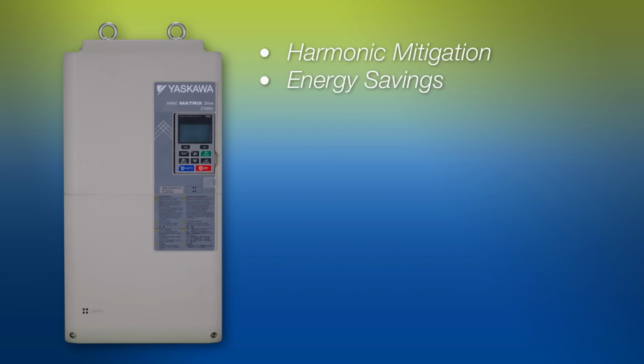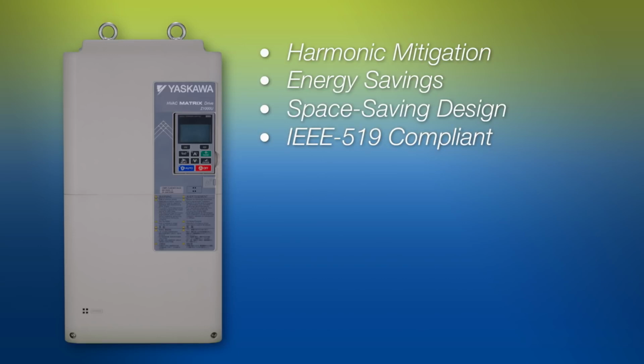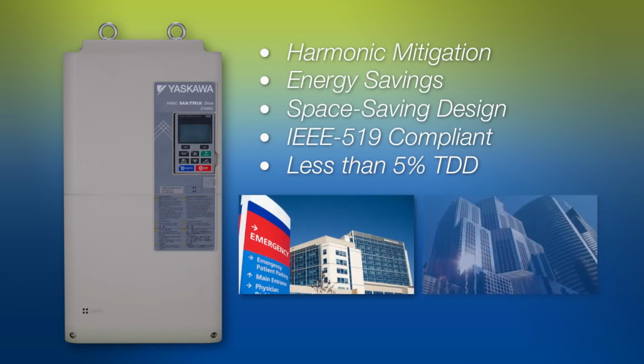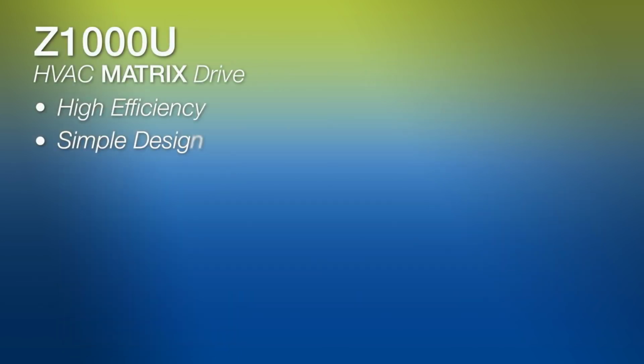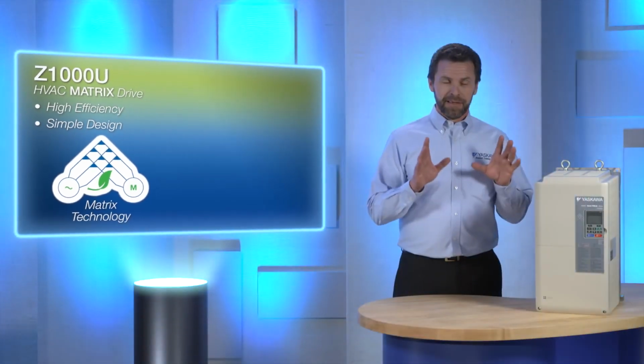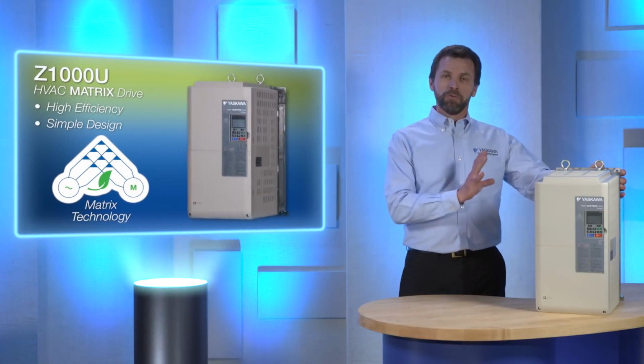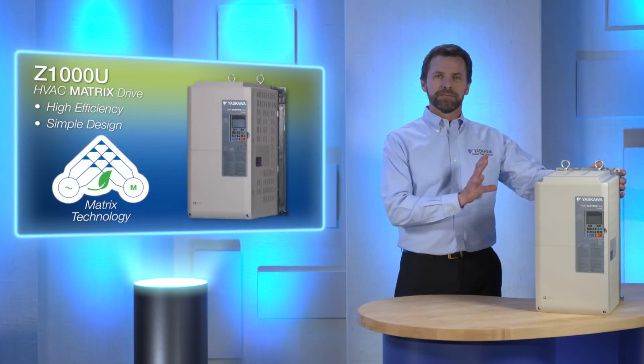It is ideal for HVAC applications that require extremely low current harmonic distortion, energy savings, and serviceability in a space-saving design. Now, because the Z1000U effortlessly meets the IEEE 519 guidelines, it can be installed in locations where harmonics must be kept below 5% total demand distortion, or TDD, such as in hospitals or commercial buildings. The Z1000U provides high efficiency with a simple design thanks to Yaskawa's engineering breakthrough called matrix technology. This is the world's first low-voltage HVAC matrix drive.